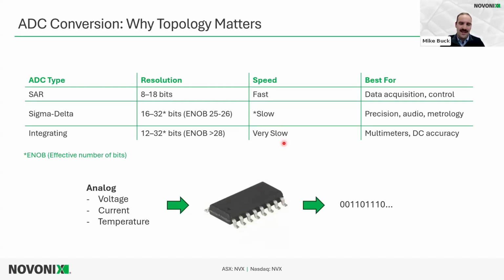The challenge is that to get that kind of precision out of an instrument, it's very slow. It has to be averaged over a lot of power line cycles. A lot of these instruments have 600 to 1,000 power line cycles before taking their initial measurement, so it can be minutes between readings.